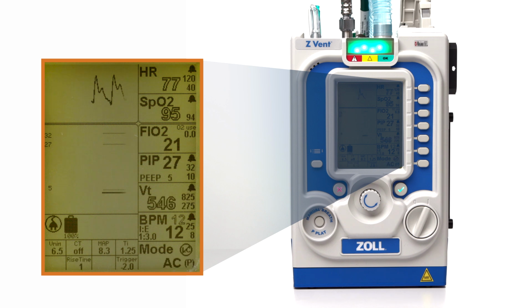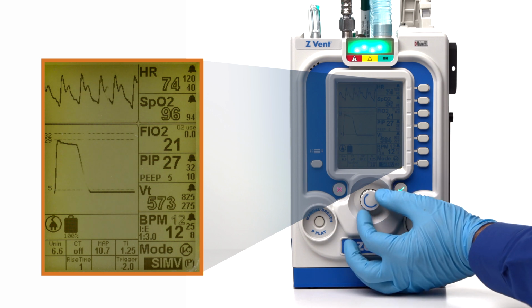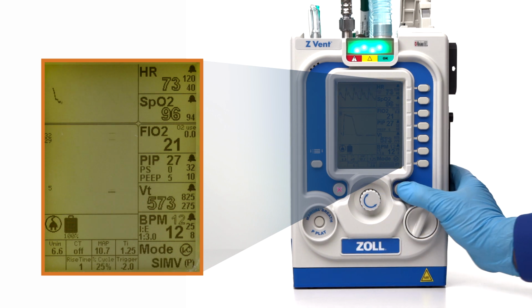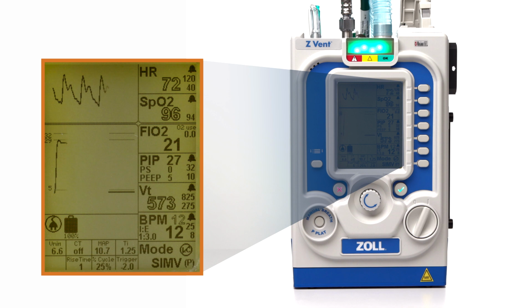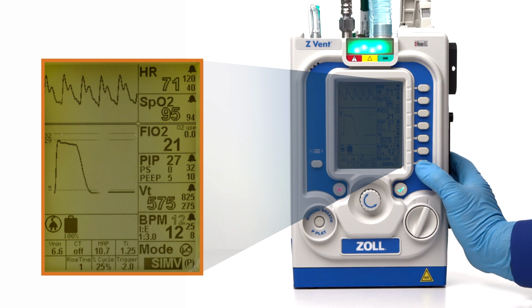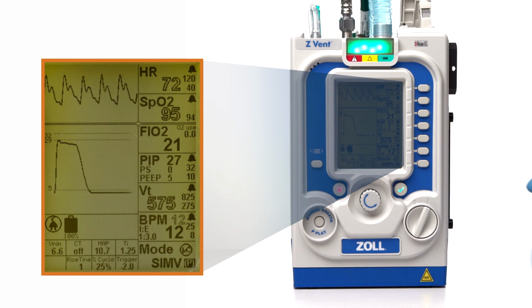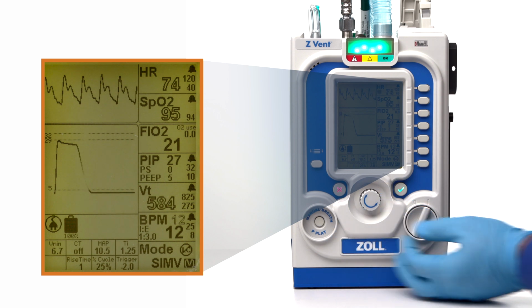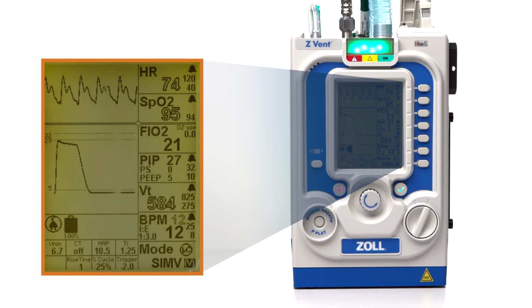In synchronized intermittent mandatory ventilation, or SIMV mode, the patient receives control breaths based on the currently set breathing rate. Spontaneous breaths are either demand flow or supported using pressure support. This is displayed as either SIMVV, indicating volume-targeted breathing mode, or SIMVP, indicating pressure-targeted breathing mode.